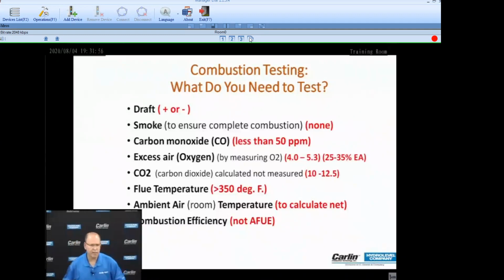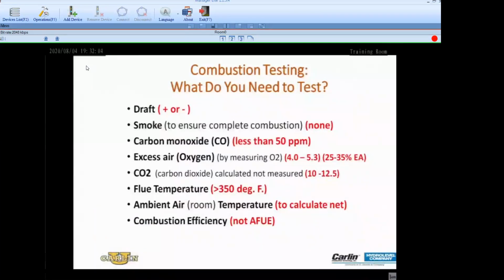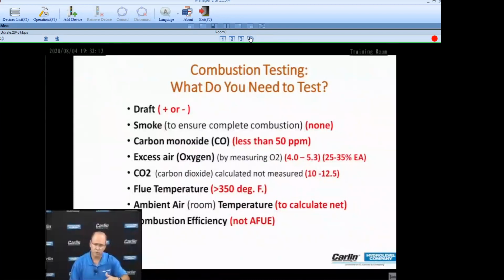We talk about flue gas temperature. Flue gas temperature, well, of course, varies by type of equipment. Certainly different as the appliance becomes more efficient, we'll see lower flue gas temperature, and it's not necessarily a bad thing as long as it's controlled properly. You don't want to reach the levels where you're condensing the flue gases either in the appliance or in the chimney. But if the appliance is supposed to maintain 450 degrees stack temperature, that's what you should be seeing. If you're not, then you need to find out why. As long as you understand why, it's all good.